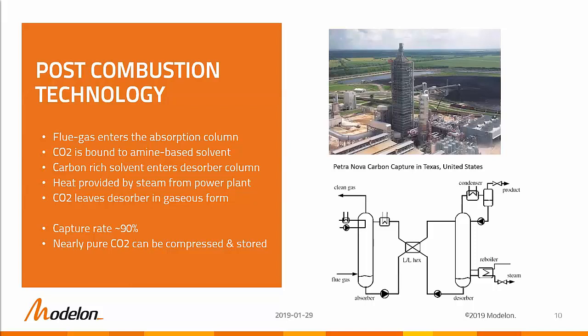It consists typically of two columns: one is the absorber and the second is the desorber. In the absorber column, the flue gas enters at the bottom and meets solvent that will chemically capture and bind CO2 on its way down.